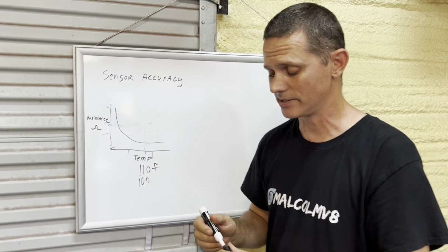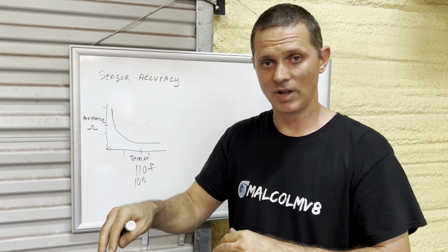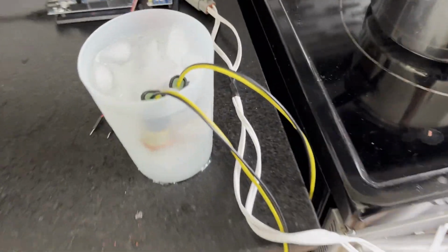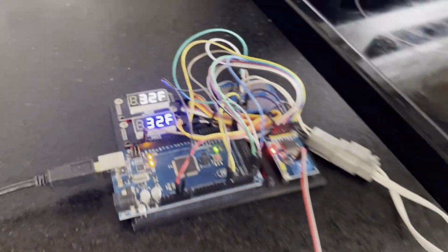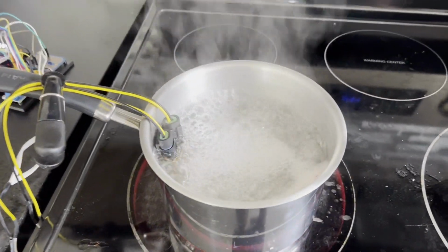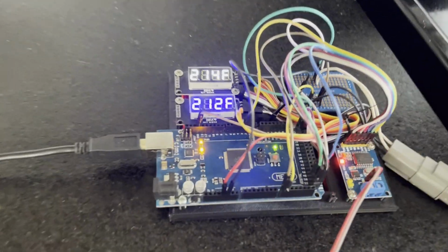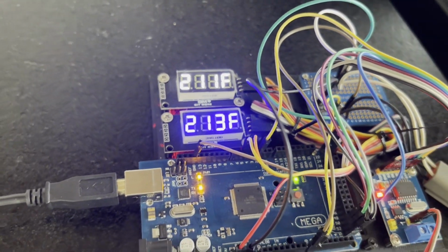And we went ahead and tested that. We put them in some ice water and let them sit there and freeze down to 32, and we observed both of our sensors going all the way down to 32 and reading that in sync. Then we did the boiling water test and pushed them all the way up to 212, and they were bouncing around 212, 214 thereabout, in a rolling, steaming boil water.